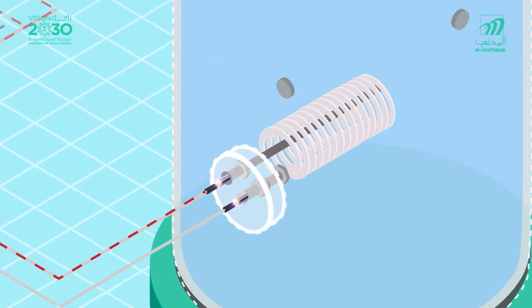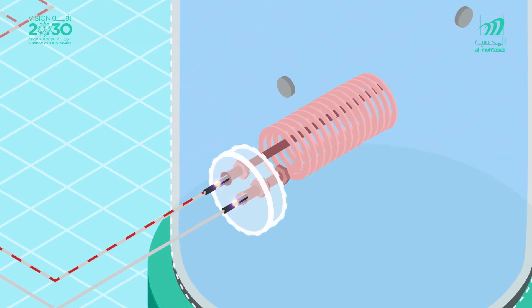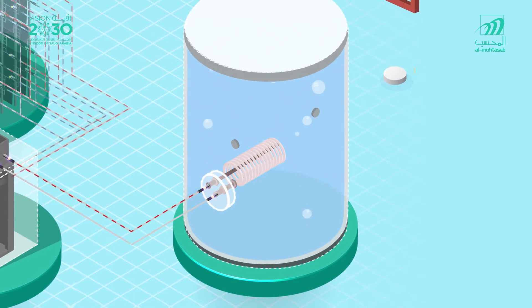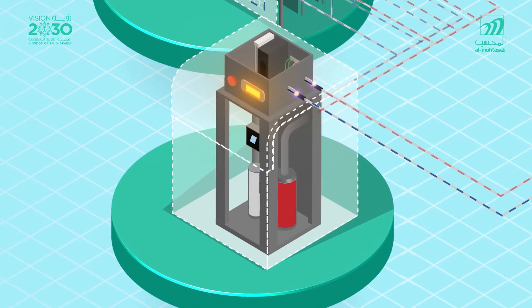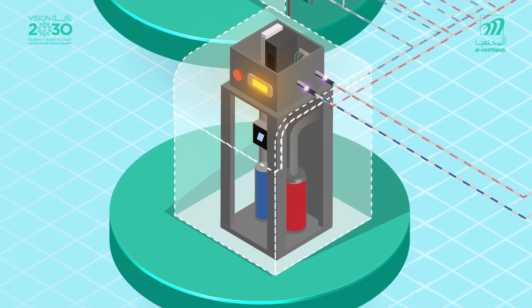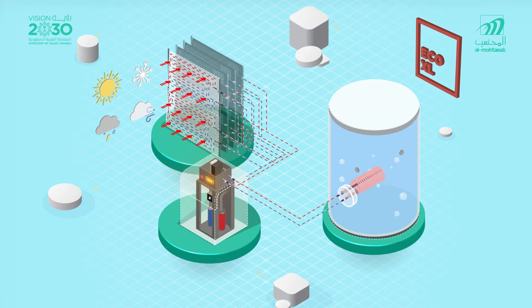The hot gas is then transferred to a highly efficient heat exchanger coil which transfers heat to the water. After the hot gas loses its heat to the water, it moves to the expansion valve which reduces its pressure and temperature, turning it into a very cold liquid. Then the cold liquid refrigerant goes back to the panels and the cycle goes on and on.